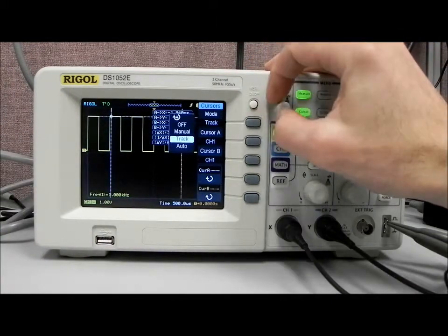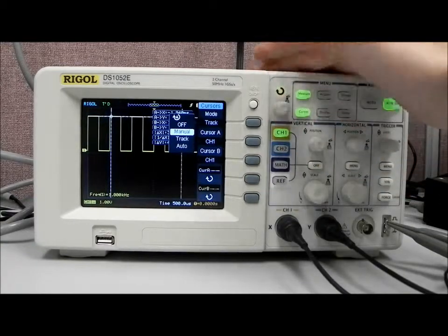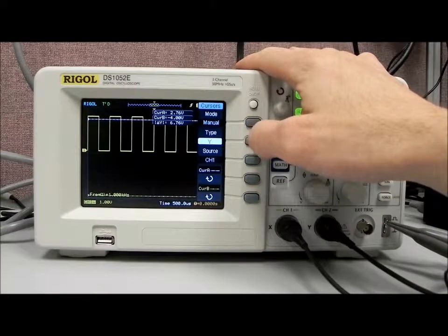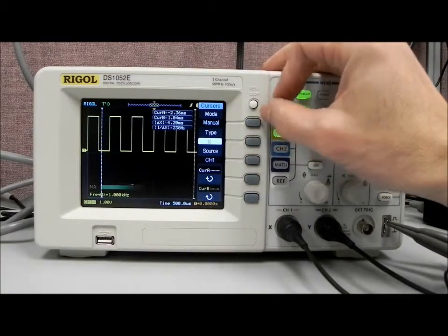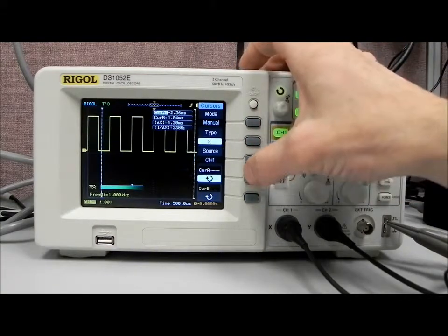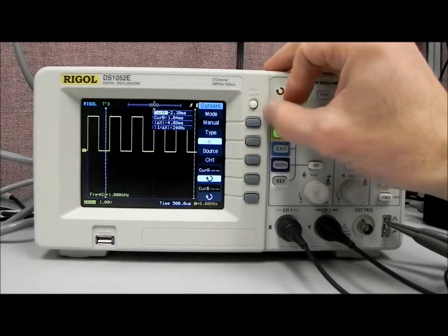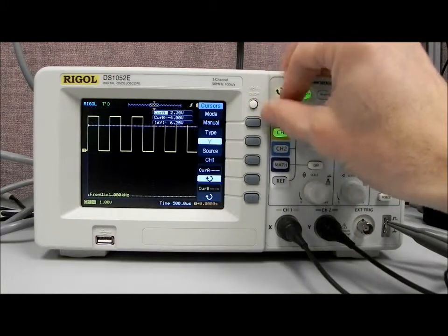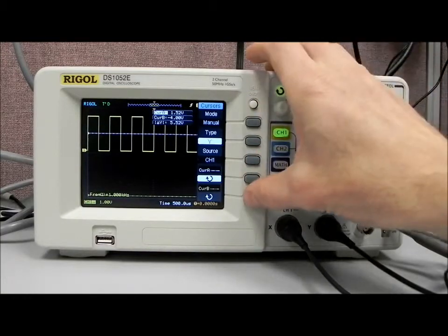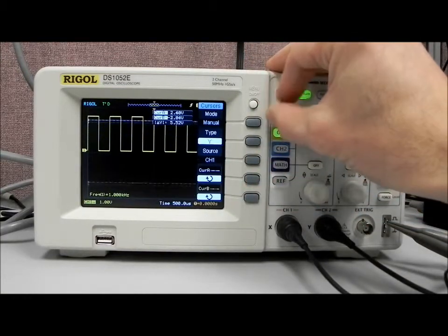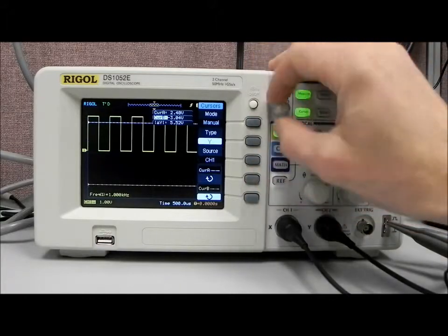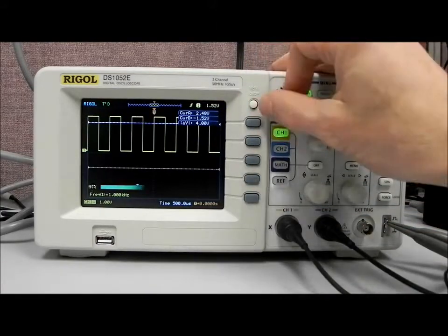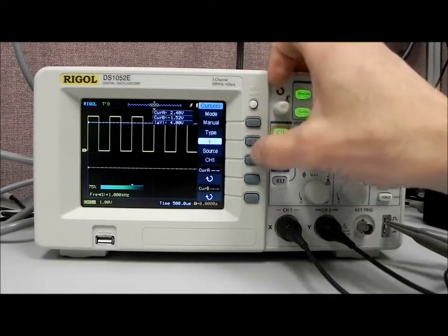If we wanted to do something a little more manual, we can go to the manual mode, and the manual mode is going to allow us to select either Y or the X-axis, and you can see they changed. Let's select A, so we can move cursor A in the X. We can move cursor A in the Y. See that? And we can also move both of them as a delta, if we wanted to do fixed or singly, which can again be useful if you were making some measurements on your waveform.